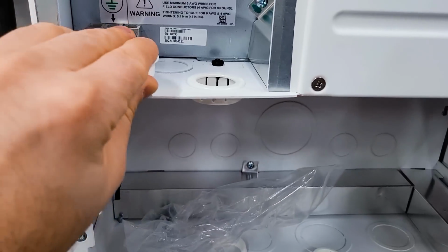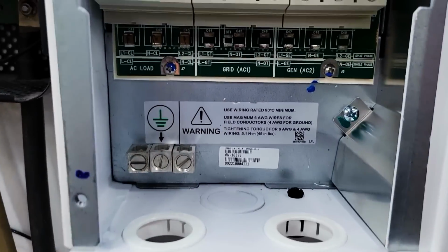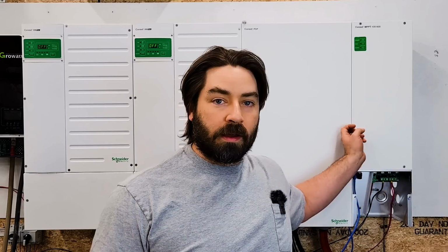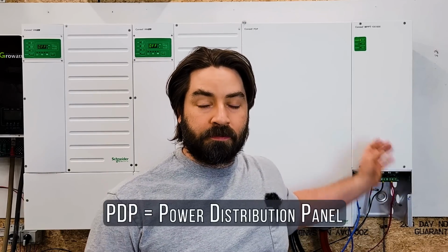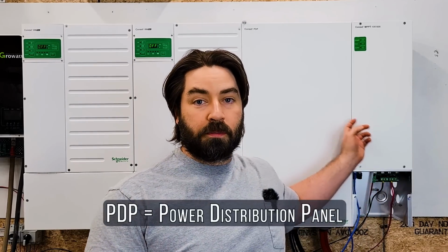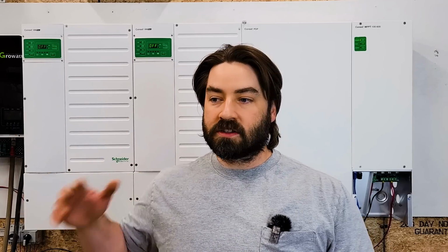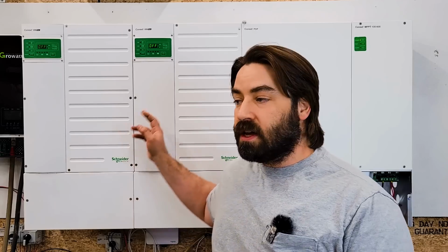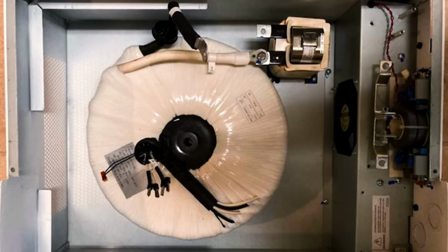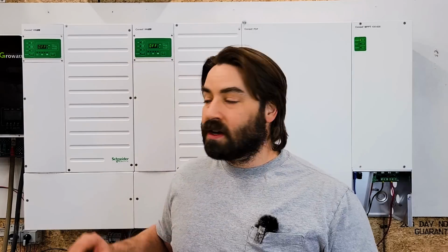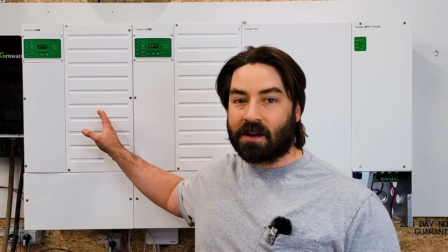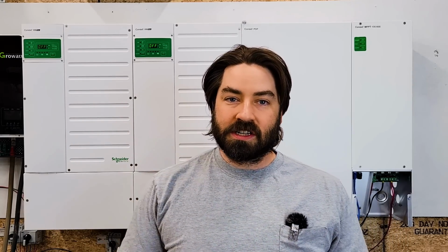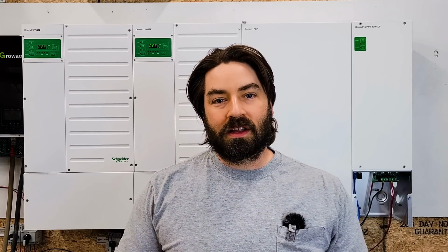Now I've finished installing a second inverter, and you can install up to 3 inverters on one power distribution panel, PDP. Or if you are running multiple PDPs, you can install up to 4 on a single phase or even more on a 3-phase system. Each of these inverters has a toroidal transformer built in, which gives you 120 and 240 volt split phase power right out of a single inverter. So you can add inverters in oddball increments. There is no other inverter that I've tested that does a better job on surges and load imbalancing between lines.